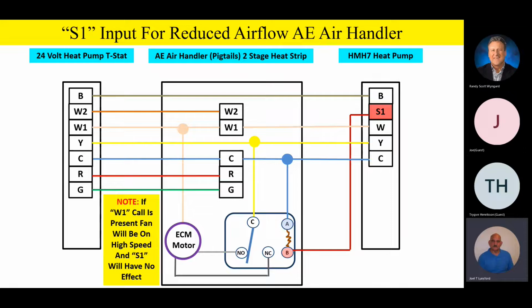Fellas, the next thing we're going to talk about is, please remember, on the AE air handler, actually all of our air handlers, if you get a W1 call on an AE air handler, it's going to go to high speed. Remember, all of our ECM motors are designed so that if they have more than one speed command on them, they'll drive to the highest speed command.